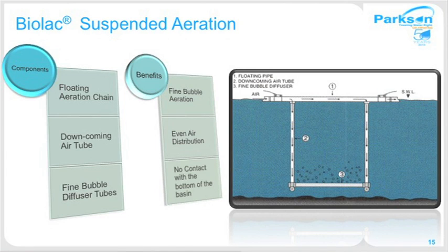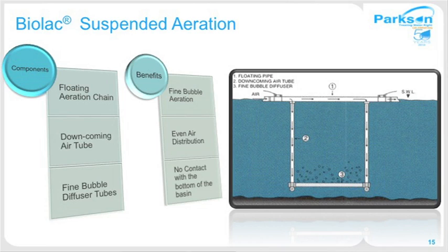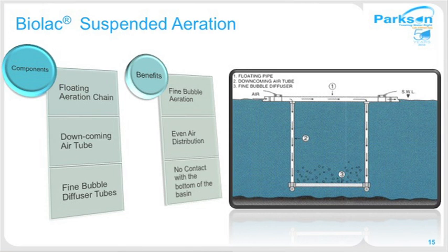The backbone of the BioLac system is the chain assemblies and the biofusers. Air from the blowers flows through the floating aeration chain on the surface — that's the first component. The airflow then goes through two downcomers down to the biofusers, which release air as fine bubble aeration into the liquid. The BioLac aeration distributes air evenly throughout the basin. The main difference versus conventional fine bubble aeration is that it's not attached to the bottom of the basin — it floats freely about a foot above the basin floor.